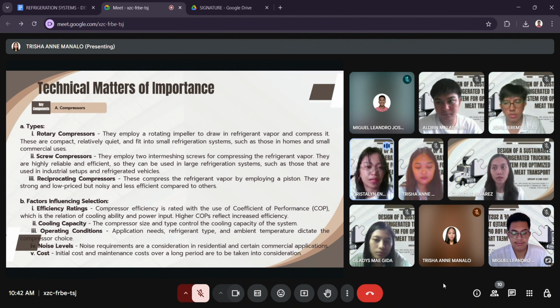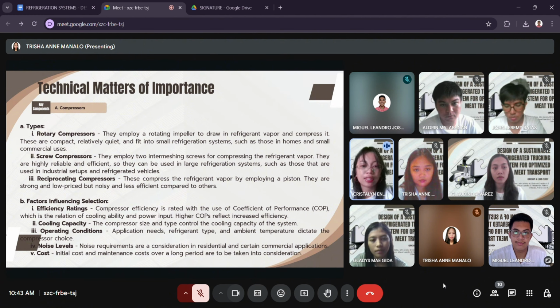Technical matters of importance. We have three types: rotary compressors, screw compressors, and reciprocating compressors. Rotary compressors employ a rotating impeller to draw in refrigerant vapor and compress it. These are compact, relatively quiet, and fit into small refrigeration systems such as those in homes and small commercial uses. Screw compressors employ two intermeshing screws for compressing the refrigerant vapor. They are highly reliable and efficient, so they can be used in large refrigeration systems such as those used in industrial settings and refrigerated vehicles.